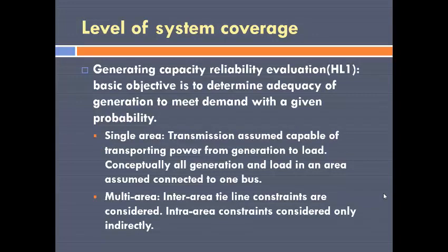In terms of system coverage, there are basically three levels at which most of the work has been done. The first level is sometimes called hierarchical level one, HL1, also called the generating capacity reliability evaluation. The basic objective in generating capacity reliability evaluation is to see how much capacity we should have so that the load or demand can be served with a certain level of probability.